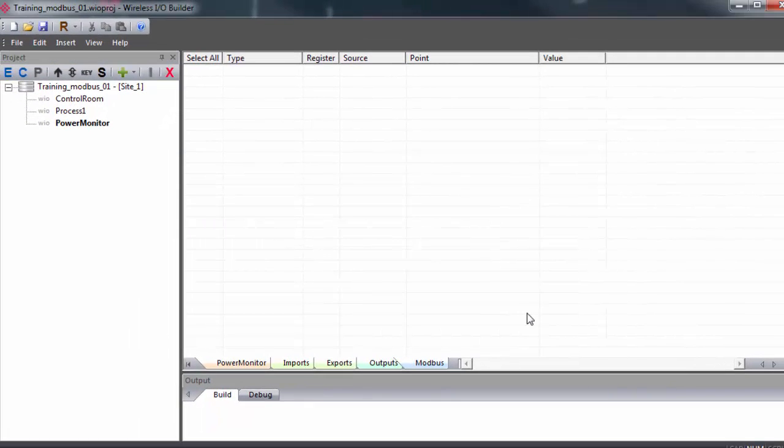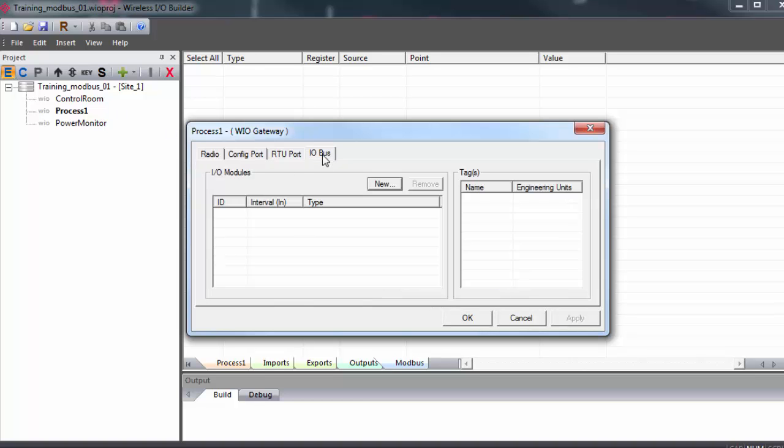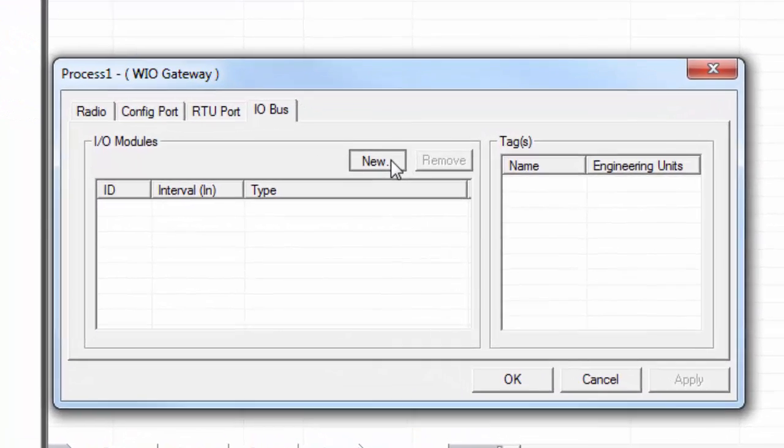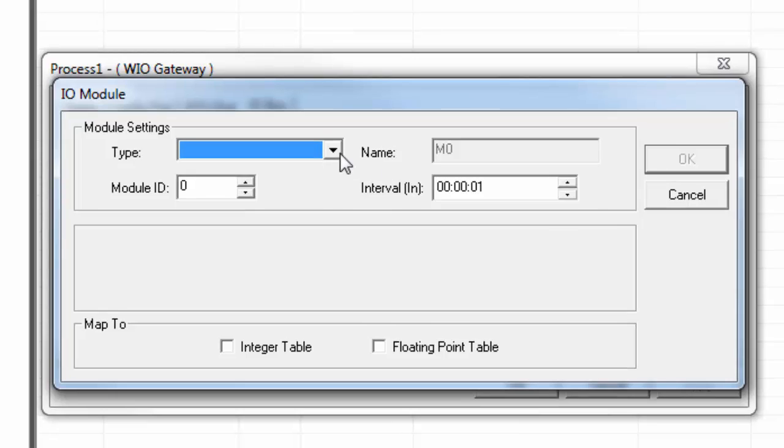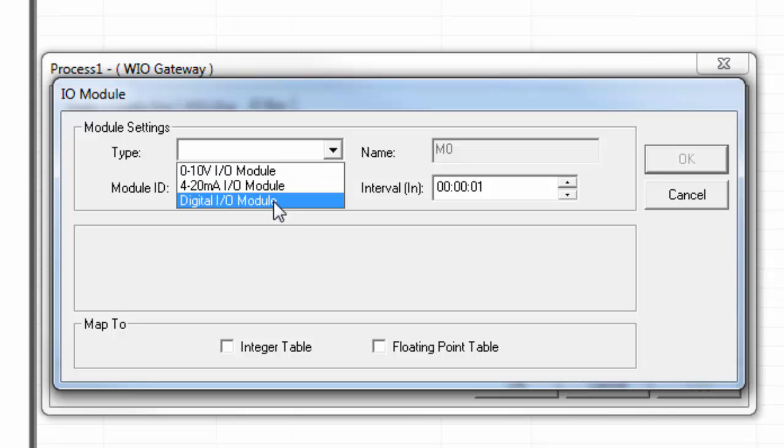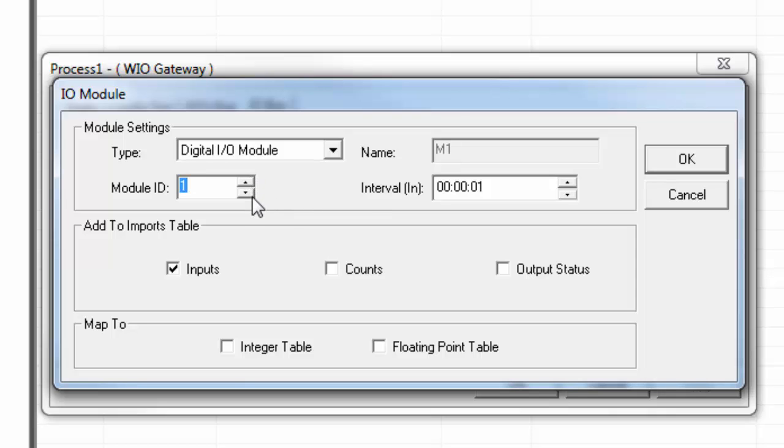So I'll double click on that gateway and click edit. And I'll go to the IO bus tab. I'll click new and select an IO module. We have three different modules to choose from. And in this case, we'll go with a digital IO module. Under module settings, the most important thing is that we need to set the module ID to match the dial setting on the module itself.